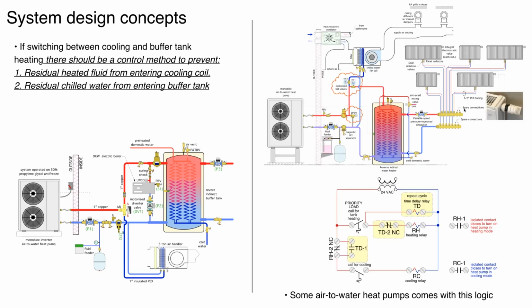Well, there are different approaches, but one approach that is kind of interesting: instead of using a 3-way motorized valve, you can use two-way motorized valves in combination with a differential pressure bypass valve. And the way this works is during a mode switch between, let's say, cooling to domestic water heating, both of these valves stay closed. And the flow basically goes through the differential bypass valve and goes right back out to the heat pump. So the only fluid that the heat pump is actually working on at that time is a small amount of fluid in this loop right here.